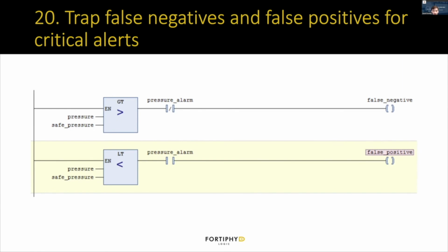So maybe you have a pressure alarm. If the pressure exceeds some value, then raise that alarm. You just have an extra check in there to see if the alarm is not happening when it should, which is a false negative, and raise that alarm. If you're getting the alarm, having that double check in there to see if the process values are actually outside of the range or not indicates a false positive, if it really should not be alarming.